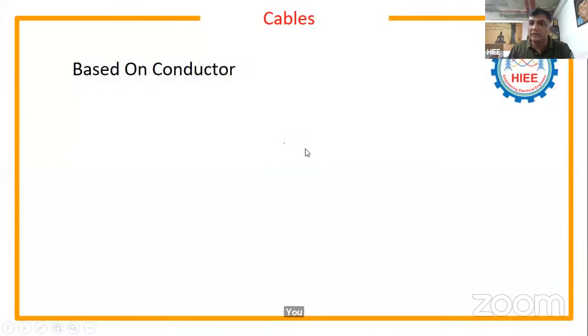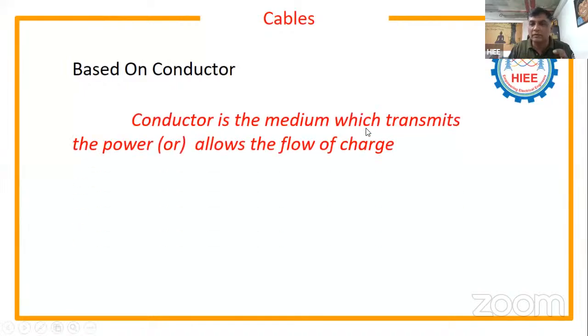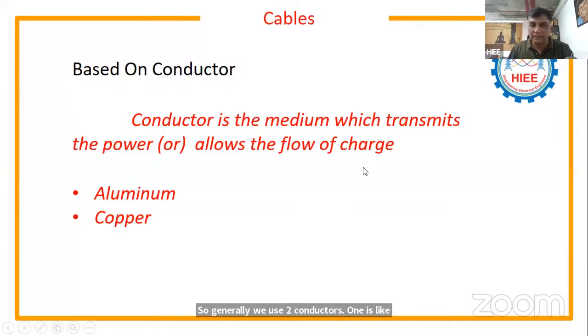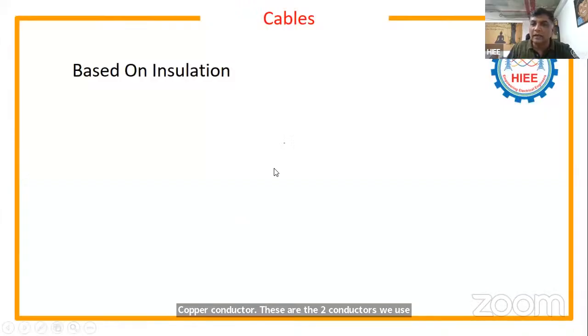Based on the conductor, generally we use two materials as conductors. A conductor is a medium which transmits the power and allows the flow of charge. One is an aluminum conductor and the other is a copper conductor. Copper's conductivity is about double that of aluminum. It depends upon the application. In India, we mostly go with aluminum conductor for most applications to make the system economical. But in the Middle East or Gulf countries, they go with copper conductor. So it depends upon the financial constraints of the project. We'll discuss where we go with aluminum and where we go with copper. These are the two conductors we use.